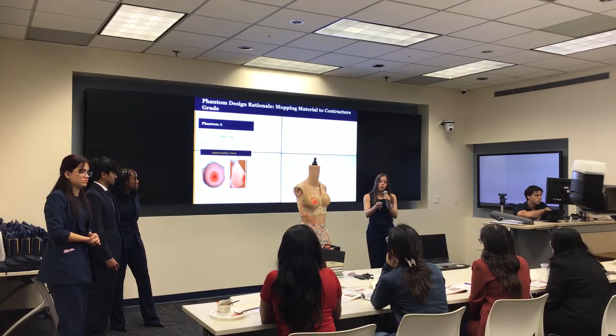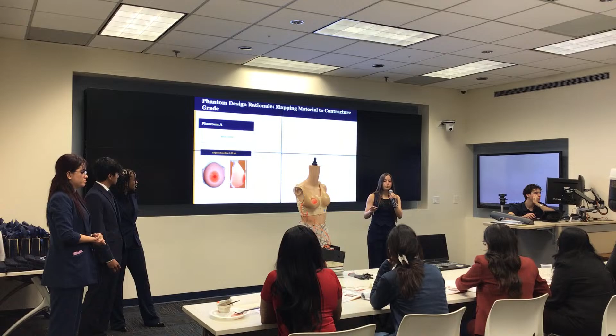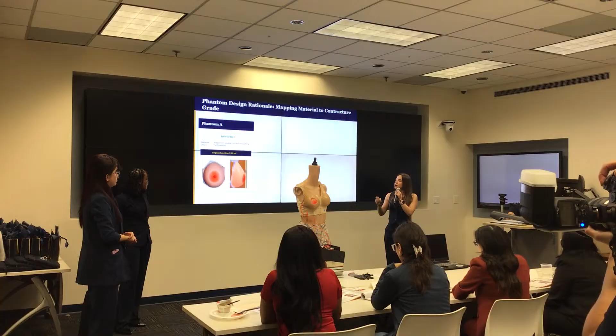To test this device, we need tissue, but real tissue is not an option at a prototype stage. So we fabricated our own: 3 phantoms that you see here, 3 Baker grades, made from Dragon Skin silicone. It's an elastomer, chosen for its tunable Shore hardness. We have our grade 1 baseline, which is this one. Phantom B uses a DS10 interior, for grade 2 to 3. And Phantom C uses DS20, which is the stiffest construct, for grade 3 to 4. This is something that does not exist in clinical literature. Right now it's assessed by palpation, and there's no public or published threshold until now.